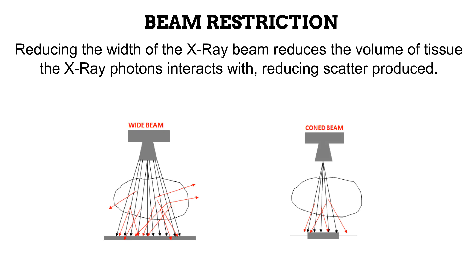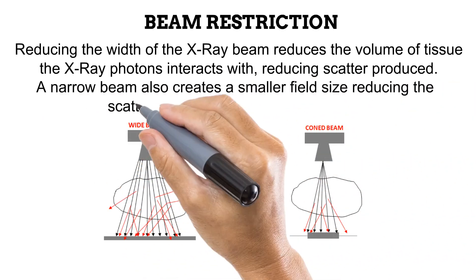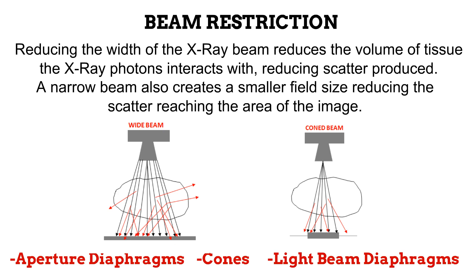The final approach to reducing the amount of scatter produced that we would be looking at is the use of beam restriction. By reducing the width of the X-ray beam, the volume of tissue that the X-ray photons interact with is reduced. When the photons interact with a smaller volume of tissue, less scatter is produced. Also, when the width of the beam is reduced, a smaller field size is created and a smaller image receptor is used. Some of the photons produced will bypass this image receptor because of its smaller size. The three common devices used in reducing the width of the beam include aperture diaphragms, cones, and light beam diaphragms.